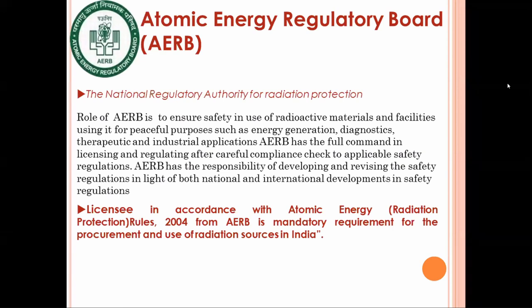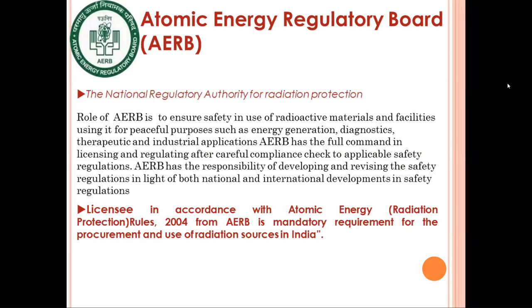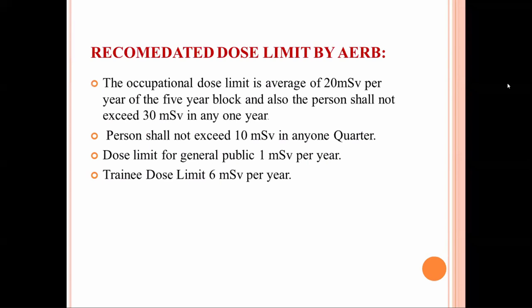The Atomic Energy Regulatory Board (AERB) monitors all radiation worker data and aims to ensure well-practiced use of radiation-generating equipment, sealed and unsealed radioactive materials. Radiation, when used properly, gives many benefits for human health — in diagnosis and treatment. The occupational dose limit recommended by AERB is an average of 20 mSv per year over a five-year block, and a person shall not exceed 30 mSv in any one year.